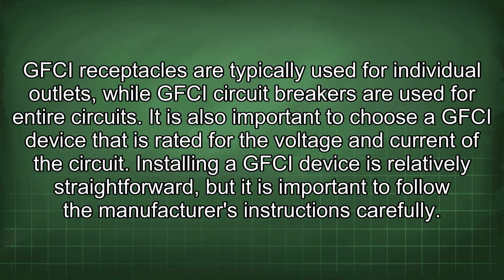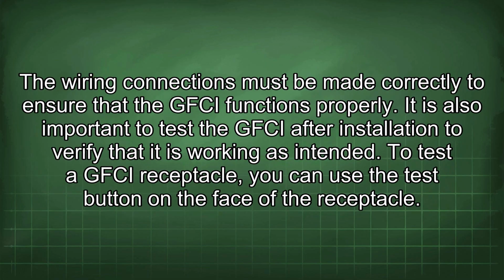It is also important to choose a GFCI device that is rated for the voltage and current of the circuit. Installing a GFCI device is relatively straightforward, but it is important to follow the manufacturer's instructions carefully. The wiring connections must be made correctly to ensure that the GFCI functions properly. It is also important to test the GFCI after installation to verify that it is working as intended. To test a GFCI receptacle, you can use the test button on the face of the receptacle.